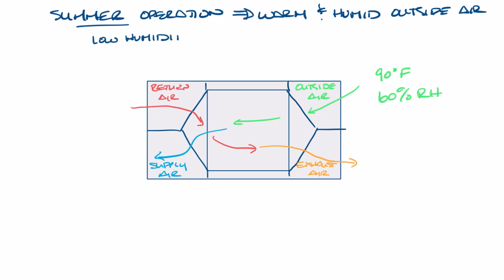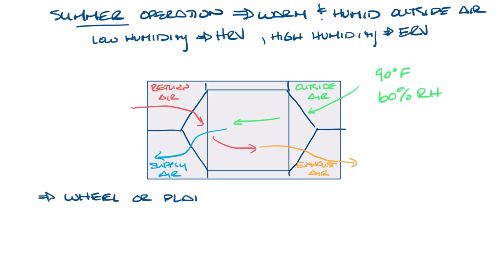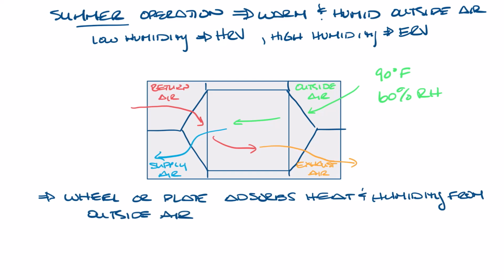If you have low humidity in your area, you may just be using an HRV instead of an ERV, so you can ignore the humidity part of this process. If you have high humidity, you might be using an ERV. The wheel or plate absorbs the humidity and heat, which is transferred from the air into the wheel or the plate. After the air passes through the wheel or plate, it's cooler and drier, maybe 80 degrees and 55% relative humidity. And you didn't need to use any energy to make that happen.